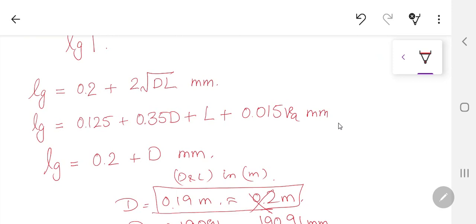You are going to be restrained by the mechanical structure of your factory, and the manufacturer or the physical persons actually working on it have to make those bearings in perfect position. So it's very difficult to have the air gap length equal to that value. It's very important that your air gap length is according to what you can practically do.